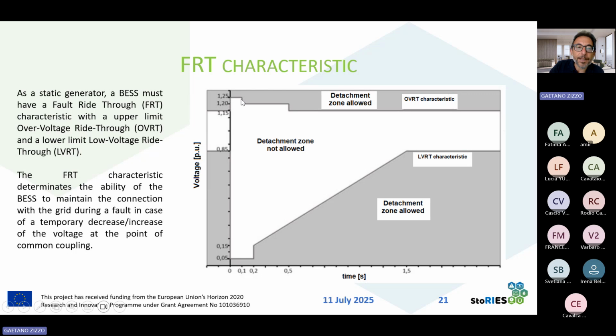This gray line represents the overvoltage ride-through characteristic that the storage system must have to stay connected during the transient that we have after the clearance of the fault. It's very important, because we can't lose regulating resources every time we have a fault in a grid. After the fault, usually we need the regulating resources, storage comprised, to intervene for restoring the previous operating condition, or stable operating conditions for the rest of the time. So this characteristic is important for maintaining regulating resources.